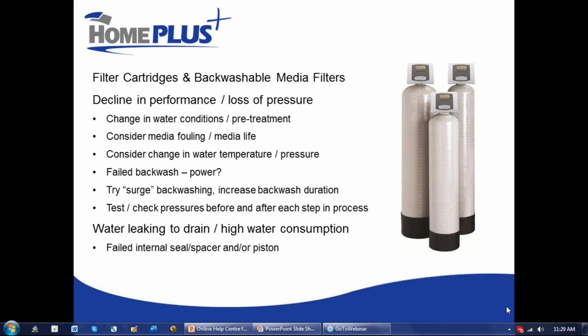Sometimes a failed backwash can be a part of the problem. Power outages are usually the cause of that sort of issue. If you're subject to repeated power outages in your area, putting your media filters on an uninterruptible power supply, kind of like a computer backup power system, is a very cost-effective way of preventing that issue. You can do the same thing with your chlorine pumps and UV disinfection systems. Especially if you're on a gravity-fed system where you're not relying on pumps during power outages to move water, you can keep your water treatment plants running quite effectively that way.